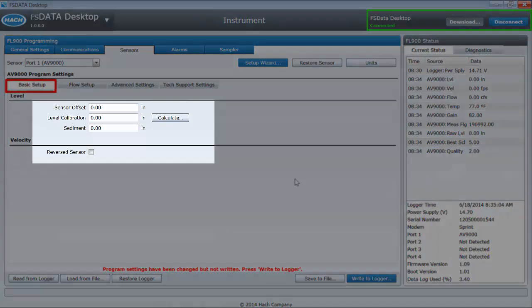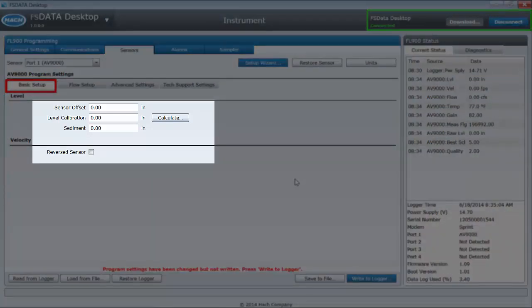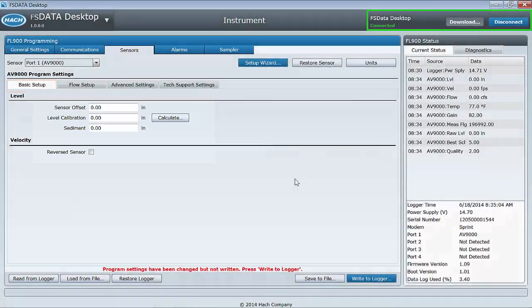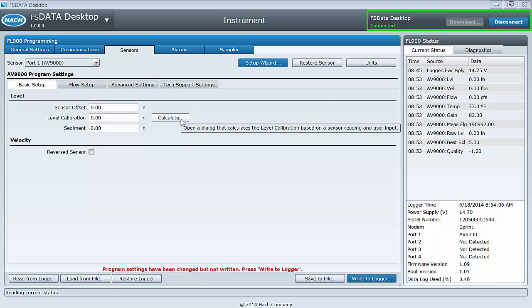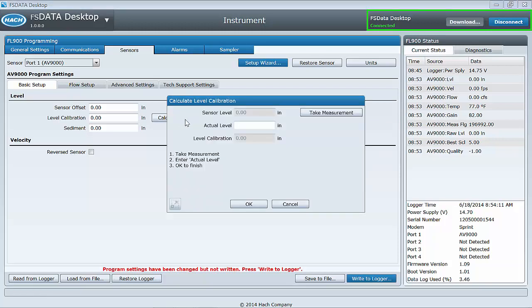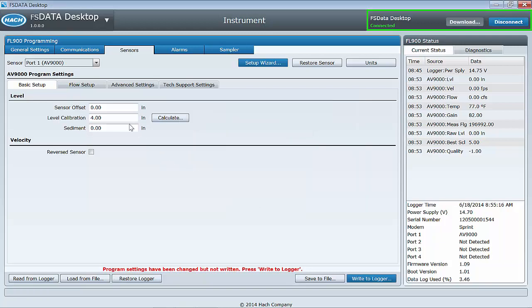The Basic Setup tab will allow you to input a sensor offset, level calibration, and sediment level. To perform a manual pressure sensor calibration, you can choose either of the following methods. Method 1. Click the Calculate button found just to the right of the level calibration input field and follow the on-screen instructions. Method 2. Enter the level measured in the channel and then click Write to Logger.